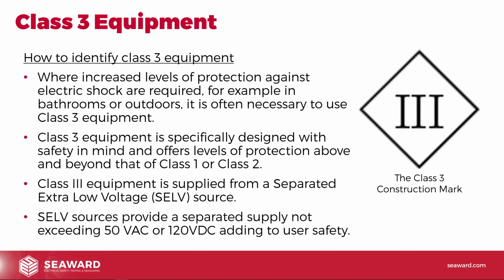Separated extra low voltage sources provide a separated supply. Now what that means is that they're not actually connected to the incoming supply. There's actually electrical separation. There's usually a transformer between the two. A bit like you might see a shaver socket sometimes in a bathroom and things like that. The secondary windings are not connected to the incoming windings. So if you get an earth fault, you're in contact with earth and you touch either the line or the neutral, there's no flow of current. There's no way the current can flow to earth because the system is separated from earth.